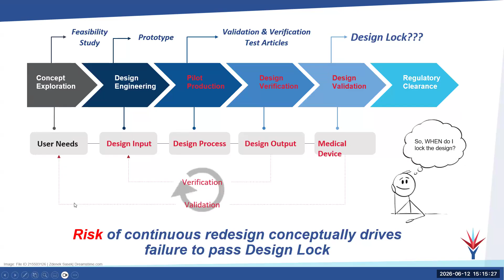What are design controls? In general terms, a set of quality practices and procedures that control the design. It's made up of the user needs, the intended uses, the unmet need you're trying to define and utilize your device to correct, how you want it to be used, and the design input requirements, where you're getting into what we need to make this thing work. Design controls ensure that the device is safe and effective. Those are the two buzzwords and the key elements, safe and effective.